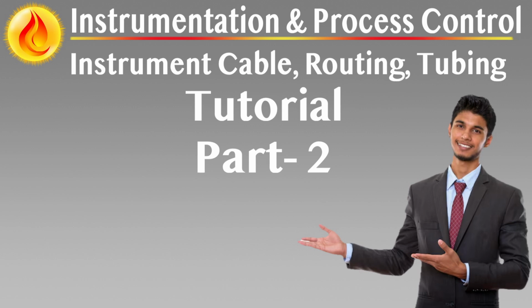Trunking and tray systems for mechanical routing and EMC shielding. Cable trunking and trays are primary support structures for routing both single and multi-core instrument cables in above-ground installations. These systems must offer mechanical protection, electromagnetic shielding, and accessibility for future maintenance or expansion. Closed metallic trunking is preferred over open tray systems due to its superior EMC performance.